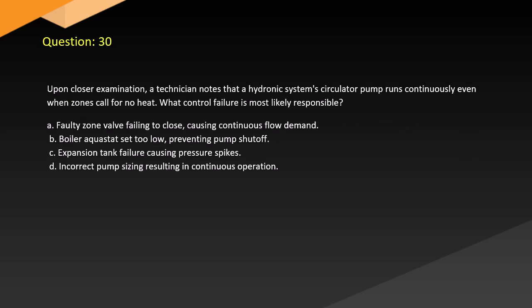Question 30. Upon closer examination, a technician notes that a hydronic system's circulator pump runs continuously even when zones call for no heat. What control failure is most likely responsible? A. Faulty zone valve failing to close, causing continuous flow demand. B. Boiler aquastat set too low, preventing pump shutoff. C. Expansion tank failure causing pressure spikes. D. Incorrect pump sizing resulting in continuous operation.